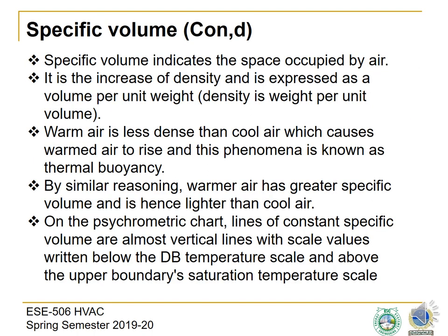The specific volume indicates the space occupied by air. It is the inverse of density and is expressed as a volume per unit weight. Density is weight per unit volume. Warm air is less dense than cool air, which causes warmed air to rise, and this phenomenon is known as thermal buoyancy. By similar reasoning, warmer air has greater specific volume and is hence lighter than cool air. On the psychrometric chart, lines of constant specific volume are almost vertical lines with scale values written below the dry bulb temperature scale and above the upper boundary saturation temperature scale.